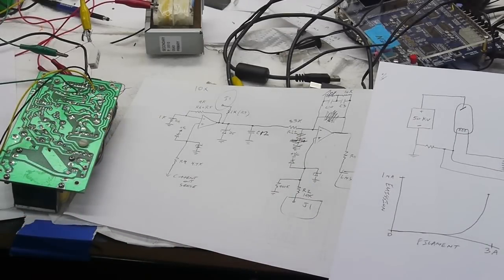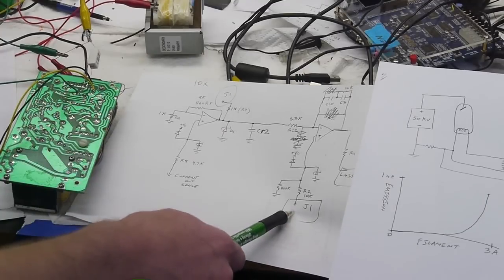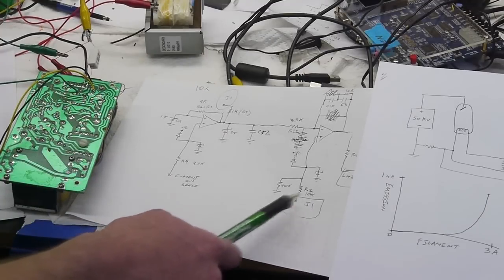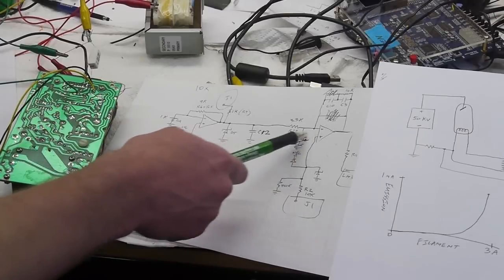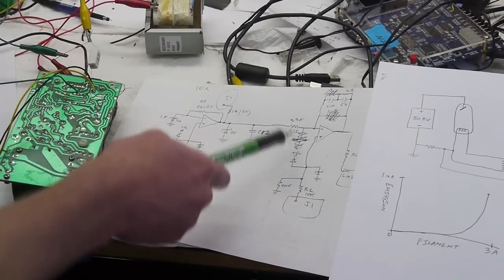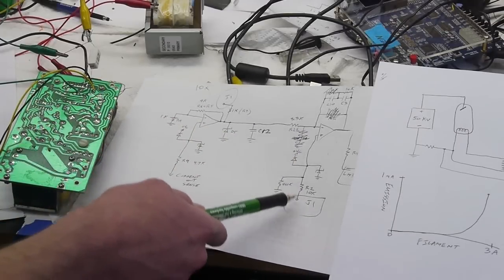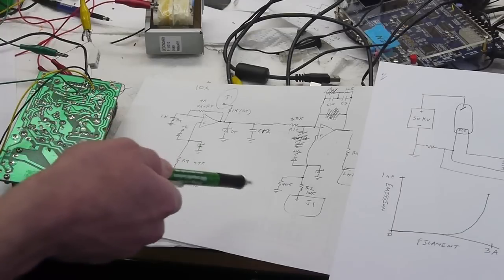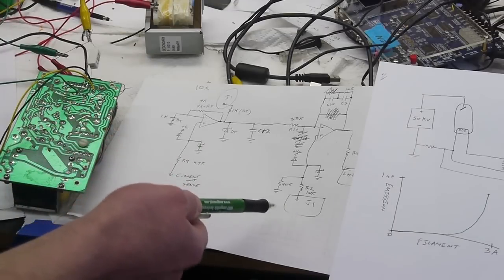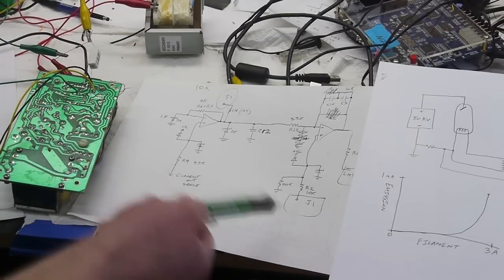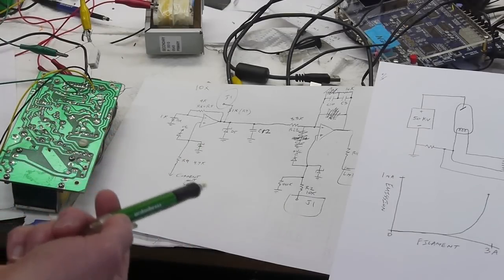So what confused me for a little while was this connection. This is actually the set current. And so they're probably using this sort of virtual ground concept. So what you do is you put a voltage here that you want this thing to match. And the voltage will correspond to the emission current, the desired emission current.